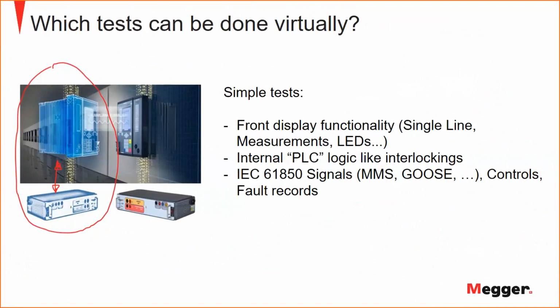So which kind of test can be done with this? Because you see, we don't stop the test set. The test set is not interacting fully with the digital twin; now it's an open loop test. We decide, and the next step will probably come that we will have full interaction between relay test set and digital twin. For the moment, it's an open loop test. Well, but many tests can still be done.